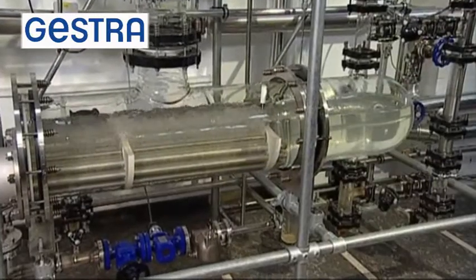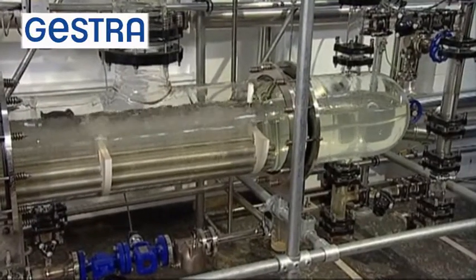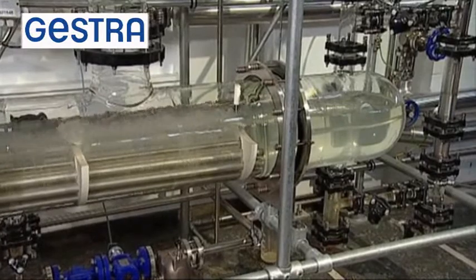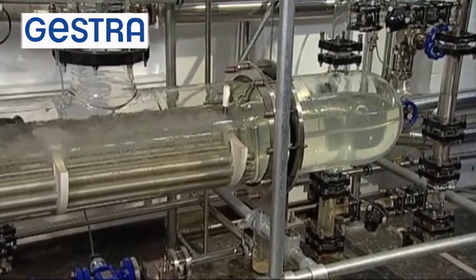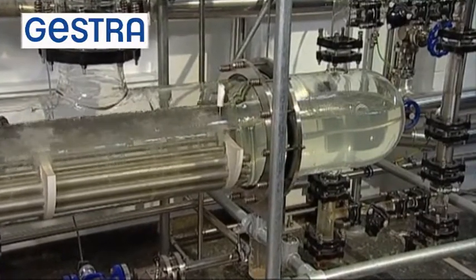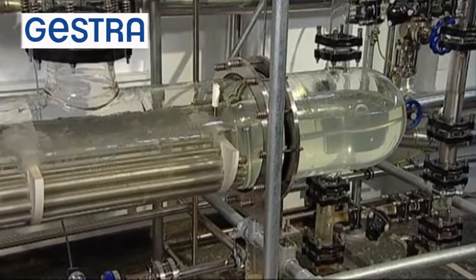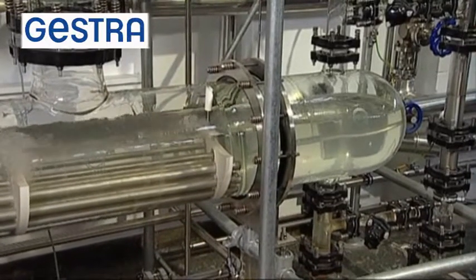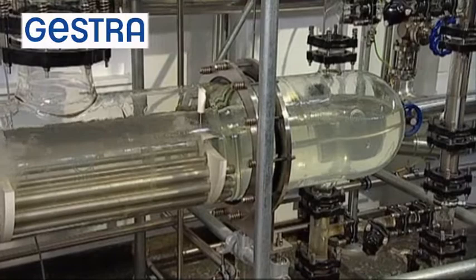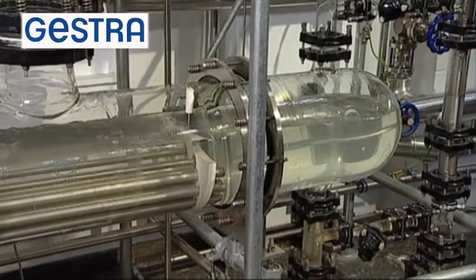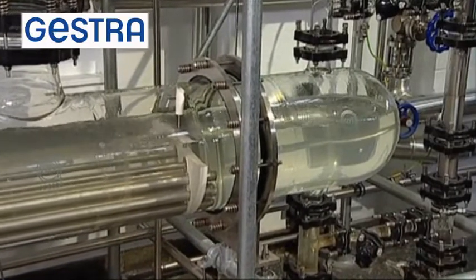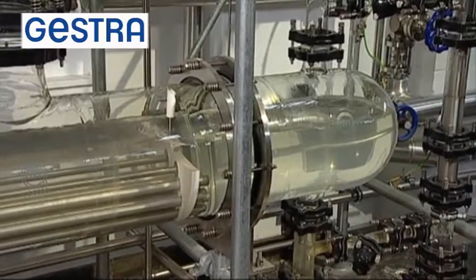A special feature of the GESTRA steam generator is that the heating rods only act on two-thirds of the glass cylinder, with the right-hand side therefore remaining unheated. This arrangement means that it takes longer for the temperature in the right-hand part of the glass cylinder to heat up, allowing us to demonstrate some special features of the feed water supply and the evaporation process.